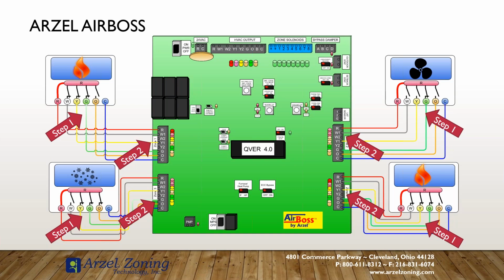But if I don't have a good voltage check from those wires, if I don't have a good resistance check to tell me that I don't have anything shorted out, then I know that I have a problem with my thermostat wire and I can proceed from there.